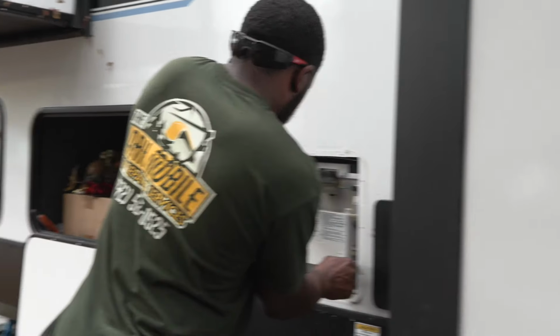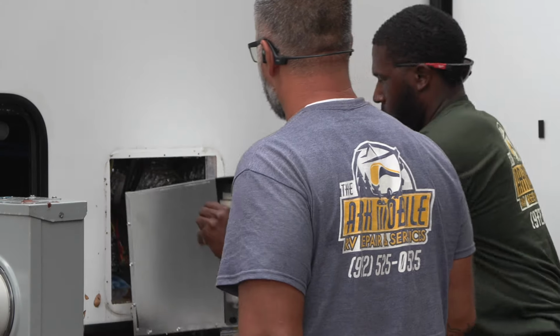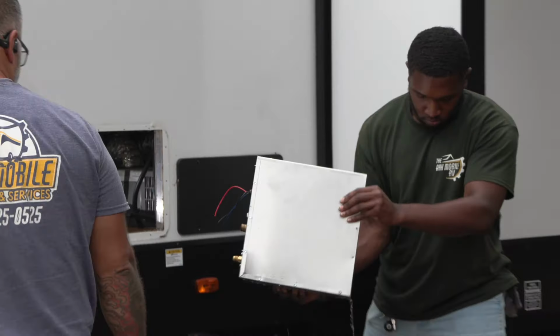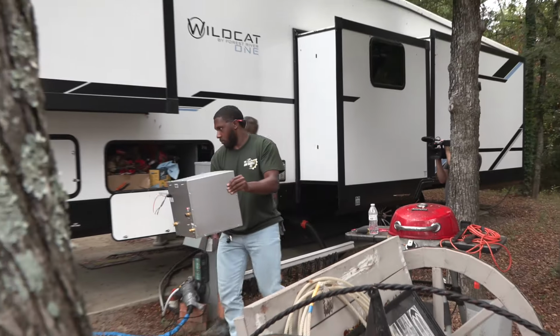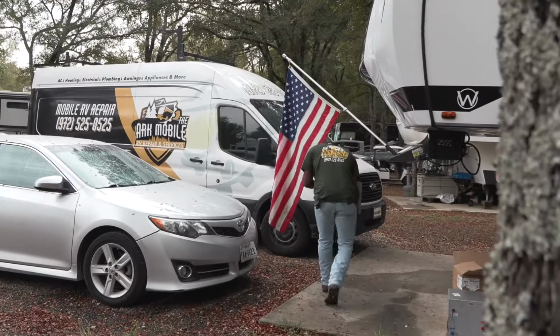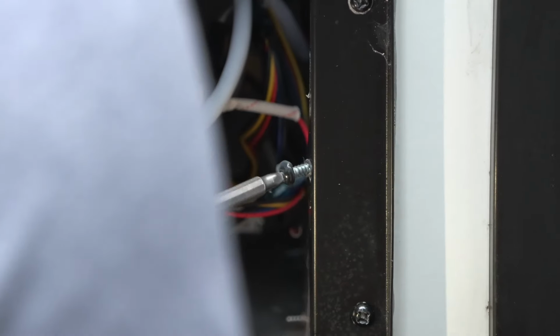All right, so we're here in Terrell, Texas. We're about to get started on our last job of the day. Today we have a warranty water heater replacement, a tankless Suburban that stopped working for a customer that just bought her rig a few months ago. We've already diagnosed it on a previous trip, and it was determined that it had a bad board and needed to be replaced. So they went ahead and sent us a brand new water heater, so that's what we're going to be doing this afternoon.